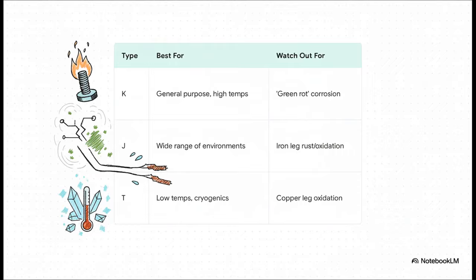It's cheap, it's reliable, it covers a huge temperature range. But you have to watch out for a weird thing called green rot if you use it in a low-oxygen environment. Then there's Type J, which is another popular one, but one of its wires is made of iron, so it can actually rust. And Type T, that's your go-to for really cold stuff, like cryogenics.